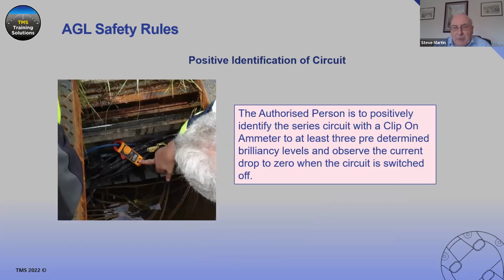This is a gentleman carrying out positive identification. He's got a clamp-on ammeter inside the pit, obviously filled with water, on the circuit that is going to be worked on. There is somebody else in the AGL switch room switching the CCR through at least three different brilliancy levels, checking that what's on the meter corresponds with what's on the CCR in the switch room, and then they know they've got, as best they can, the right circuit.